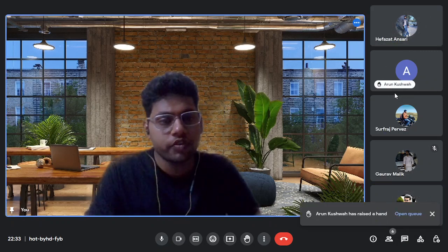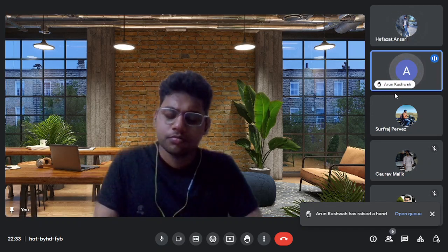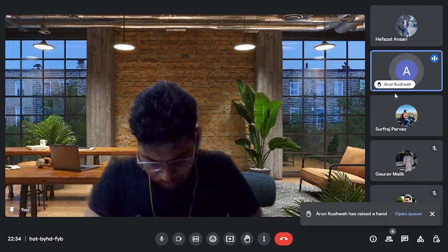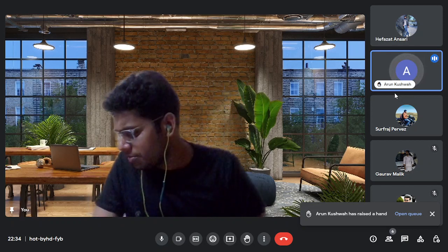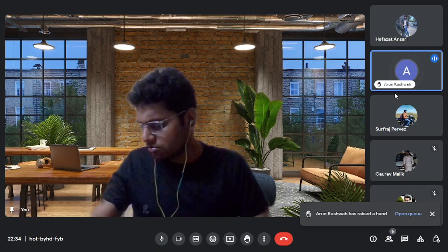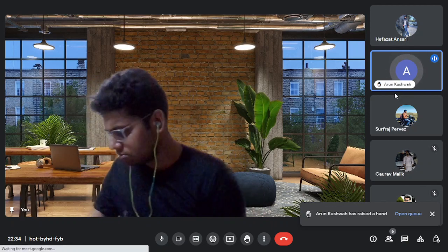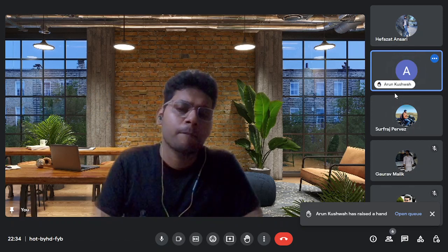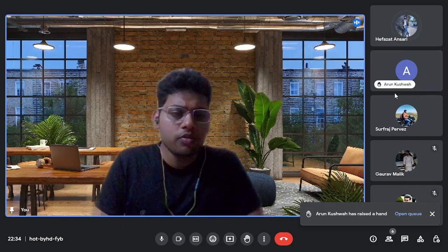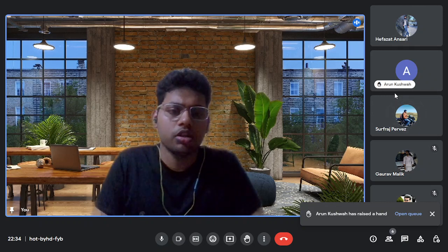Arun, try it. Yes, up to some amount of air can be handled by the centrifugal pump, that is 1 to 5 or 6%. Above 6%, the pump can go air blind, so the pumping can stop there, as air is compressible and the pump won't run with the air, and after air blinding, the pump will soon run air dry. In the starting, you were going right, but after that, it needed some more details.